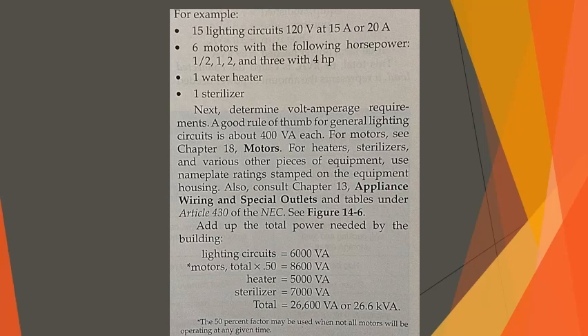Add up the total power needed by the building. Lighting circuits equal 6,000 VA. Motors total times 0.5 equals 8,600 VA. Heater is 5,000 VA. Sterilizer 7,000 VA. And the total is 26,600 VA or 26.6 kVA. Note the 50% factor may be used when not all motors will be operating at any given time.